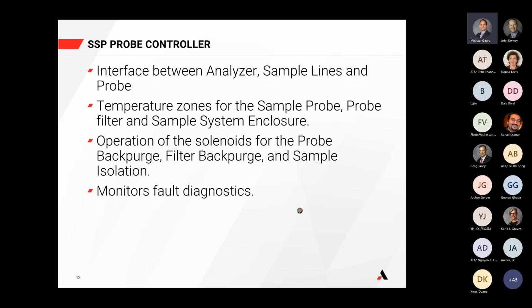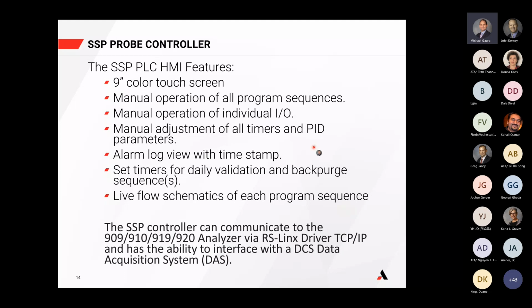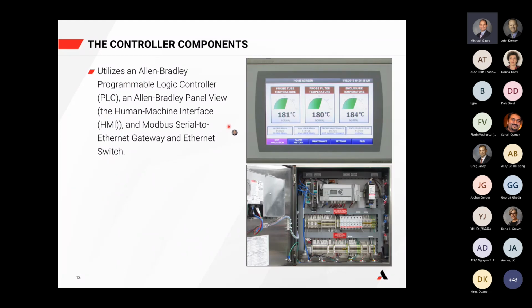So I'm going to try and go to the next slide, Rod, and if it won't, okay, there we go. The controller components: the real brains behind this is an Allen Bradley MicroLogix programmable logic controller, which is essentially a PLC. And then we tie that to an Allen Bradley PanelView HMI. So this is a touchscreen HMI. And I'm going to walk through the various screens that are available on this PanelView display here.